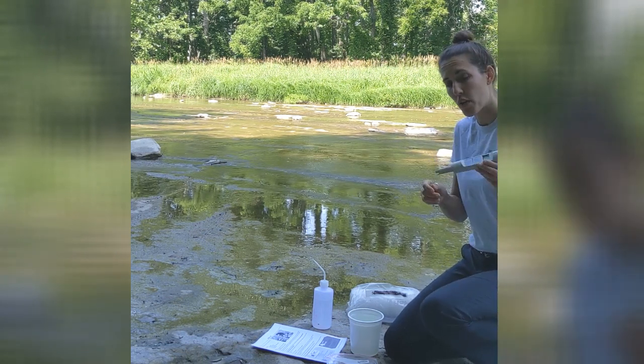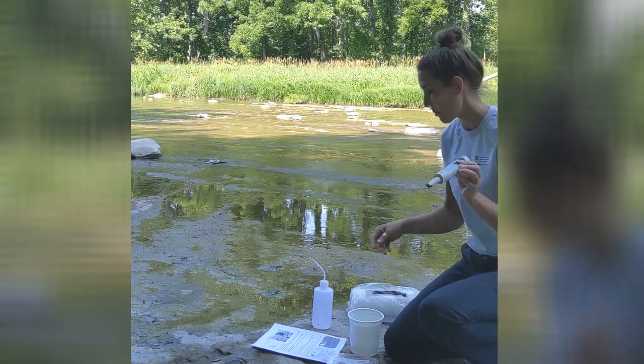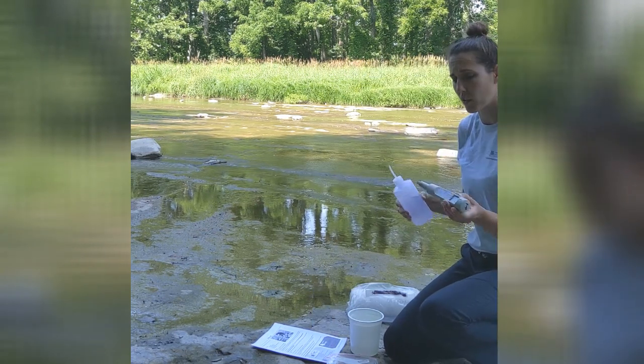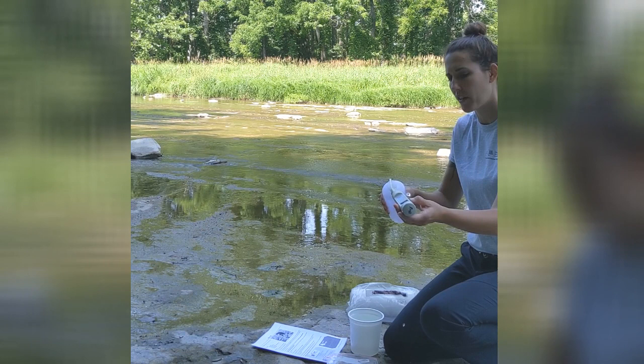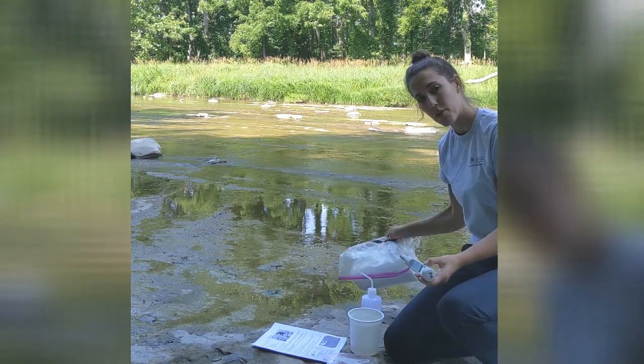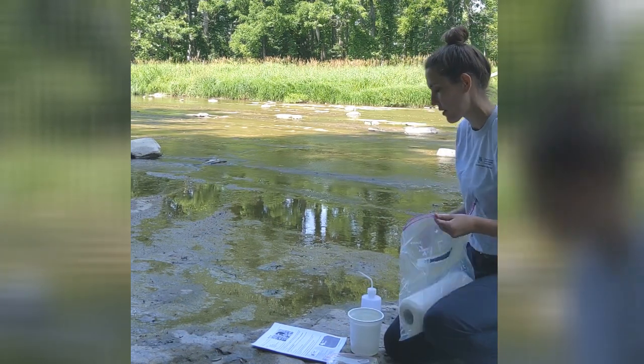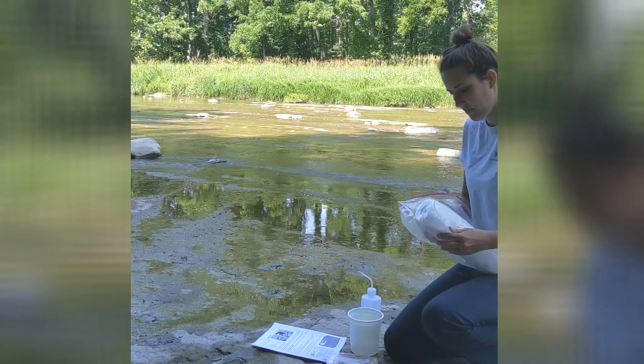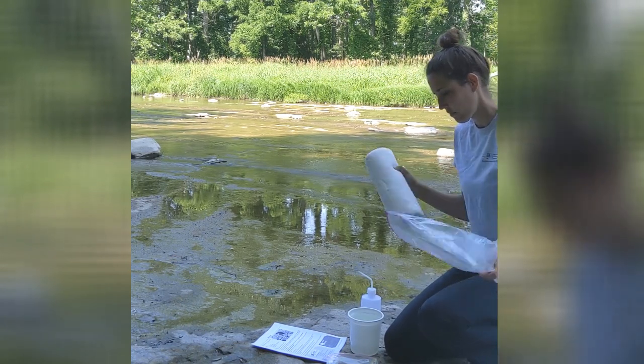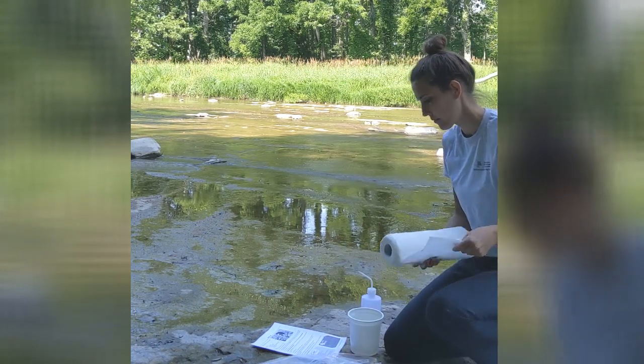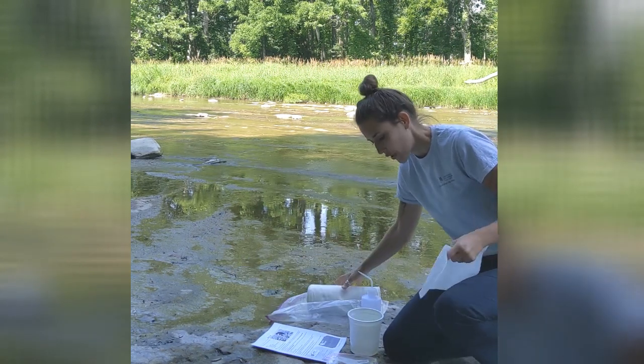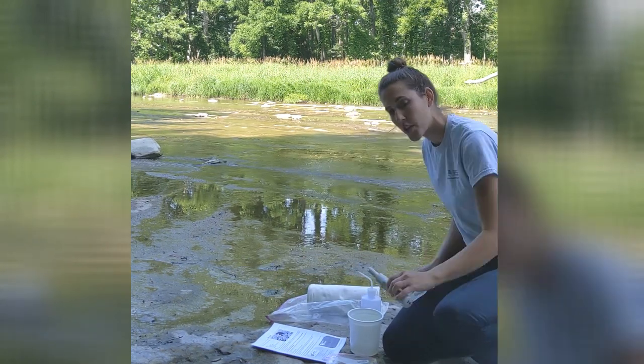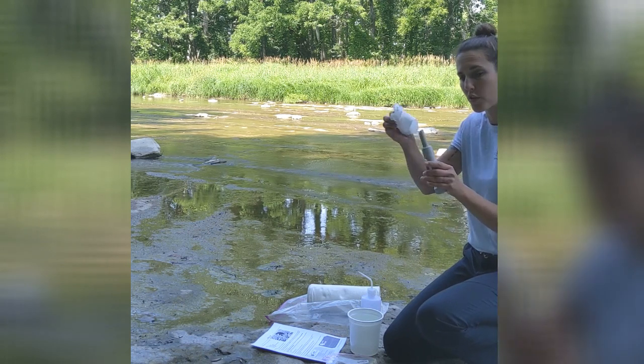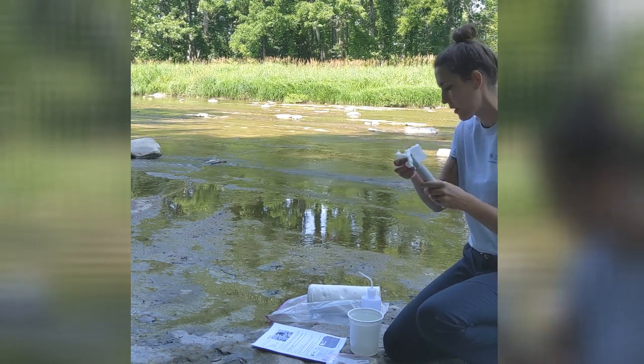Then you're going to rinse the electrode, which is down here at the bottom of the meter, with distilled water. So you can just squeeze that down there, rinse it off, and then you'll dab it dry using some paper towels. You want to make sure that while you're doing this, you don't accidentally touch the electrode at all with your fingers. Use the paper towel to dab it dry.